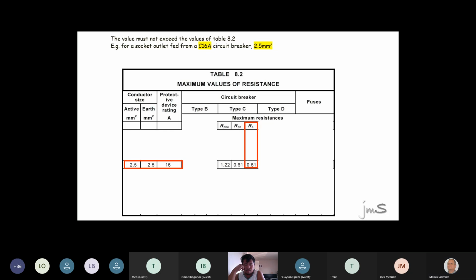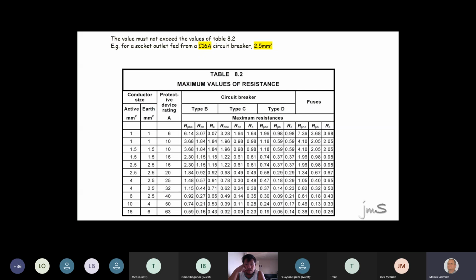How's that sound? Now, I'm going to go back a couple of photos, and I would like you to tell me an answer. And now you're going to look at this and say, oh golly, I don't know. We're doing a light. It's a 10 amp circuit breaker, C-type, C10 amp breaker, 1.5 millimeter wire. So it's this line here, 1.5, 10 amp breaker. What is the resistance of the earth wire? Right, well done. The maximum ohm reading will be 0.98 of an ohm.